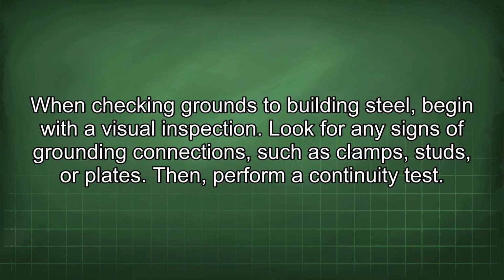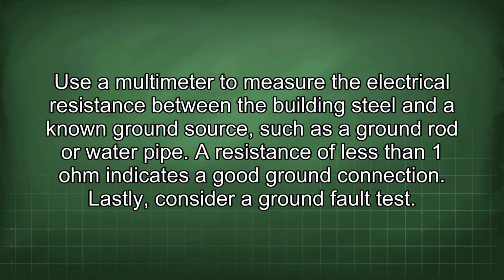When checking grounds to building steel, begin with a visual inspection. Look for any signs of grounding connections, such as clamps, studs, or plates. Then perform a continuity test. Use a multimeter to measure the electrical resistance between the building steel and a known ground source, such as a ground rod or water pipe. A resistance of less than 1 ohm indicates a good ground connection.